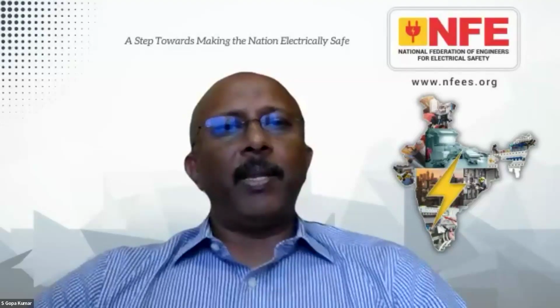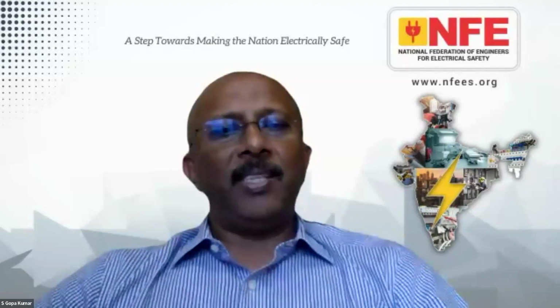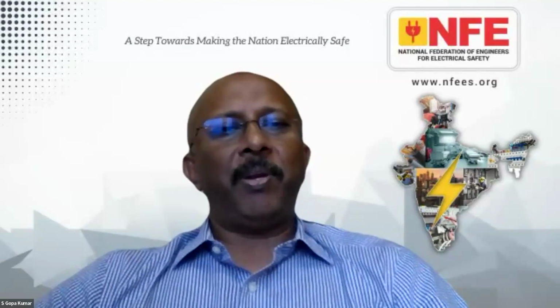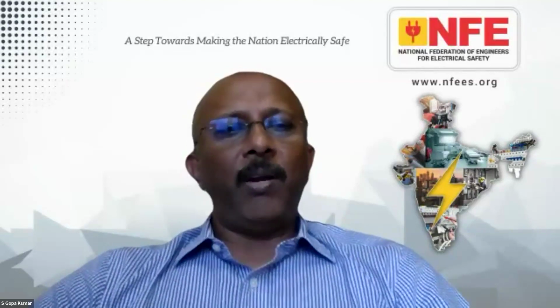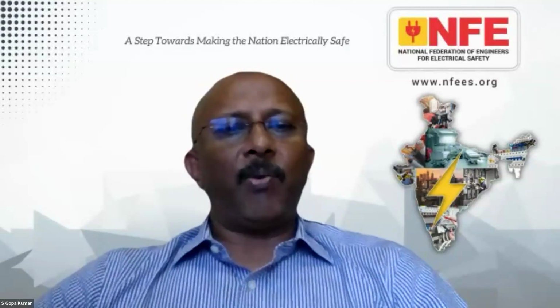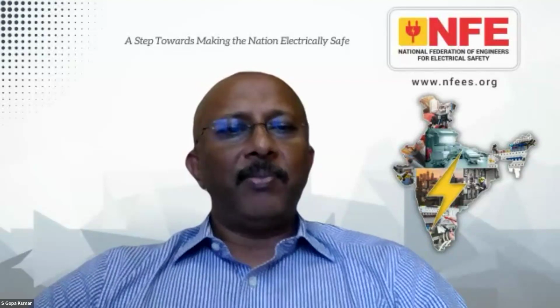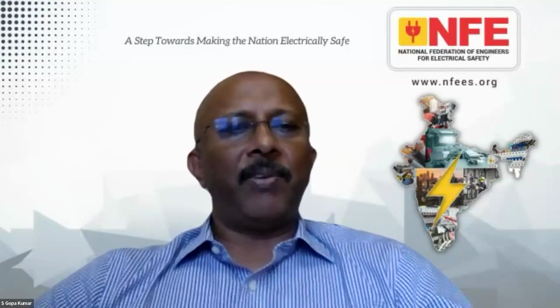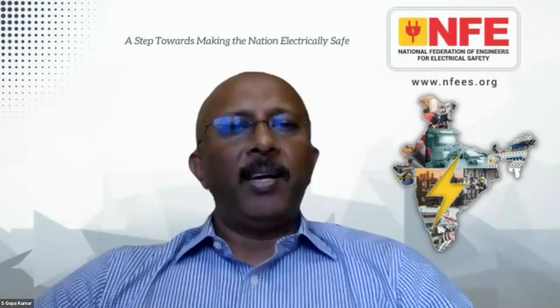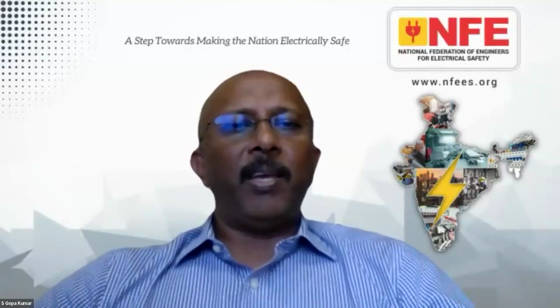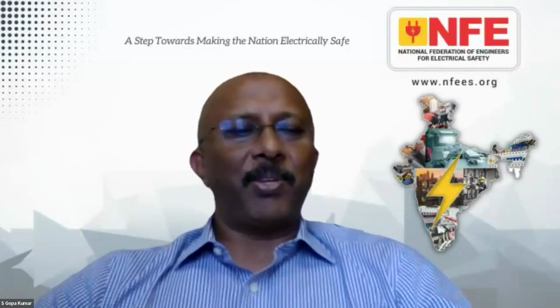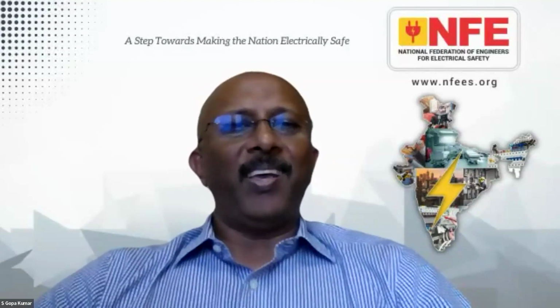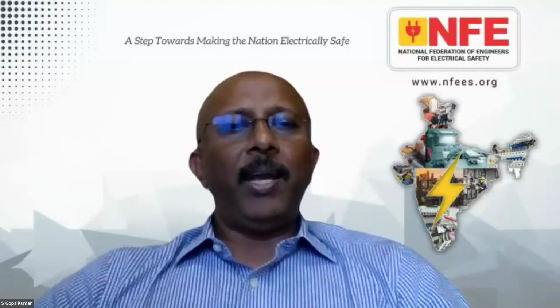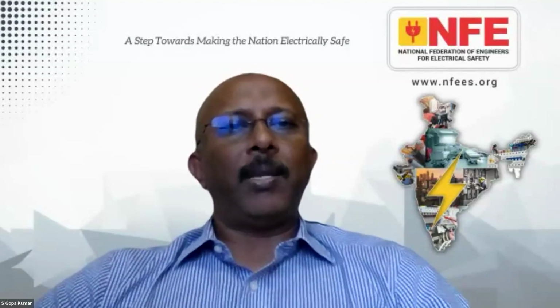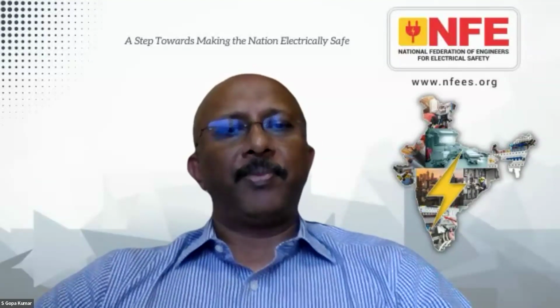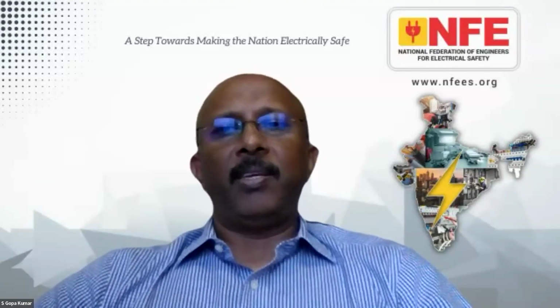At the moment, sir, there is no facility available in India. It's a question of time. These requirements came only recently. Over a period of time, there will be several companies. What I recommend, and what I do, is we have multiple testers, several meters of different current ratings. Once in 2 months we buy a new meter, because the manufacturer gives calibration for 1 year. Then we check the accuracy between 2 meters just to ensure that the old meters are in good condition. This is the only possible way according to me.